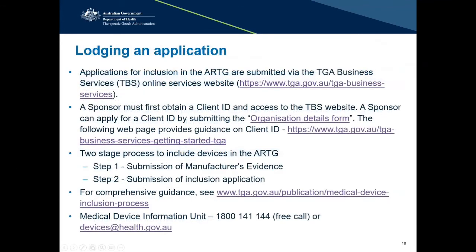And on this slide here, we have information on how to lodge an application. It really is a two-step process. So the first step is for the sponsor to submit their manufacturer's evidence, and this is the QMS certification associated with the medical device. And once the evidence is accepted, the sponsor can then proceed with the actual application for the medical device. And we have comprehensive guidance available on our website. And we also have a team that can assist with general inquiries, and they can be reached via email or phone. And I've listed that at the bottom of this slide, and that's also available at the end of the presentation too.